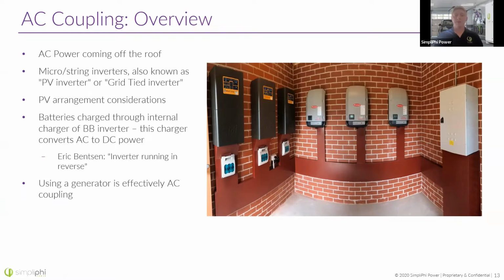Now, the main reason panels are put in this way is often because either it's easier to wire or you're first installing a system without batteries and you don't even know that you might add batteries later down the road. So putting in a system without batteries, you'd be using what they call a string inverter, which is a full string of panels coupled on the roof to an inverter on the ground or the wall, and then also the option to use microinverters on each individual panel. These can also be called PV inverters or grid-tied inverters.